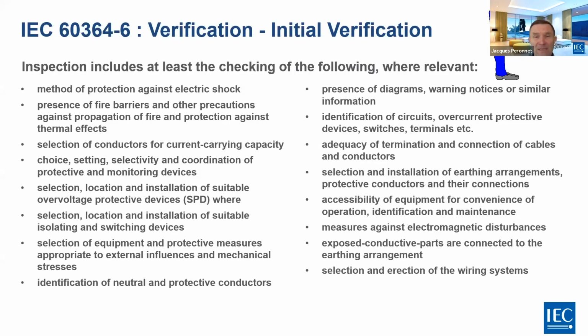Based on this principle, the inspection includes at least the checking of the following where relevant. So you have to check the method of protection against electric shock. You remember it was described in Part 41. In most cases it is automatic disconnection of supply, but it could be double or reinforced insulation, electrical separation, or the use of safety or protective extra low voltage.